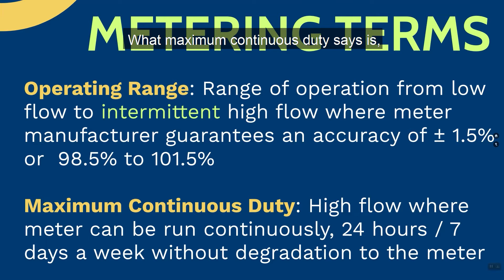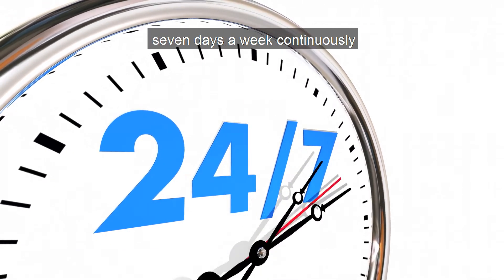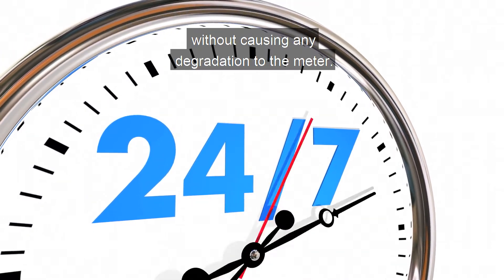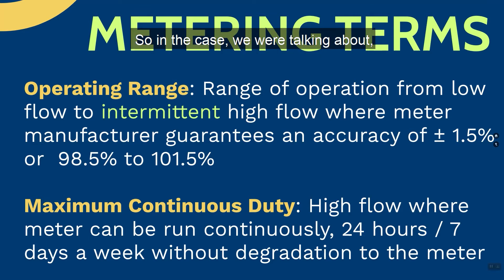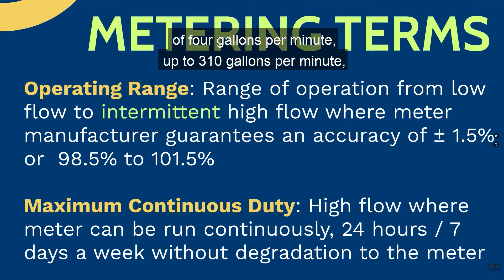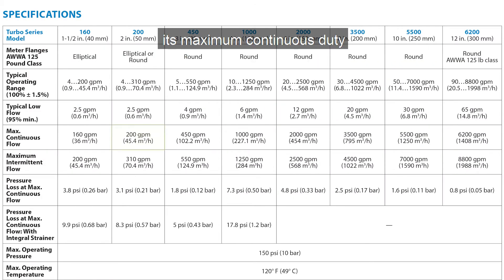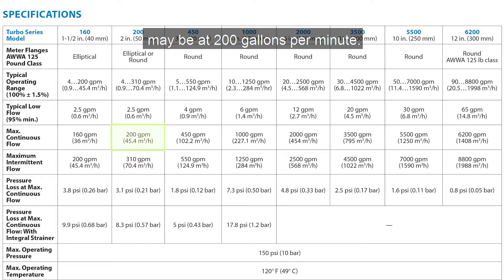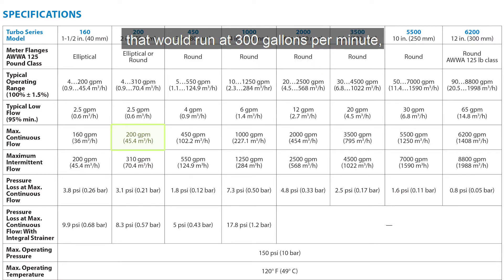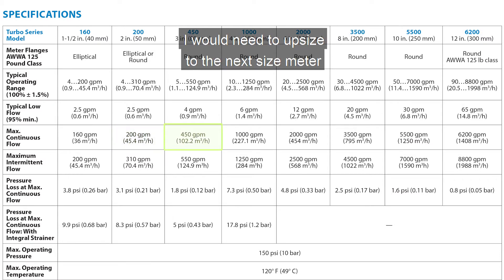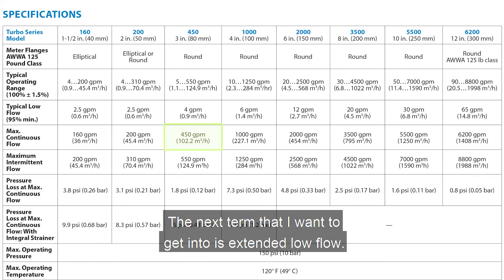Maximum continuous duty is where the meter can run 24 hours a day, seven days a week continuously without causing any degradation to the meter. So in that same example — a meter with an operating range of four gallons per minute up to 310 gallons per minute — its maximum continuous duty may be at 200 gallons per minute. If the application runs at 300 gallons per minute most of the time, I would need to upsize to the next size meter in order to fit that particular application.